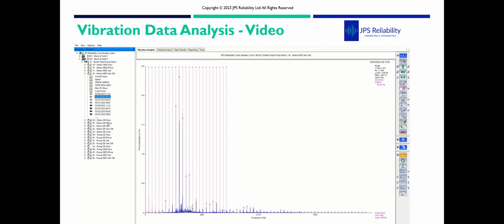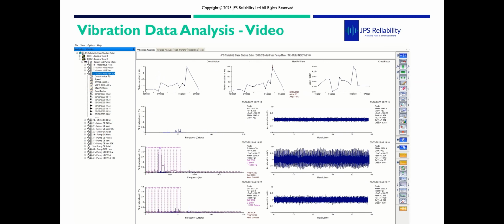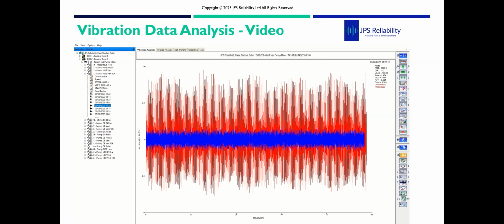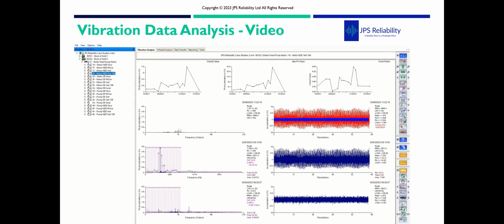We can jump into the peak view data, and you can see here the change straight from when the bearing was with defect and no defect. But the big giveaway, as I say with these bearings, is your high frequency. You can see it there. And what's pretty cool, again, another function of the software, is we can actually overlay before and after. So when you want to show someone, look, this is the bearing screaming, you know, 20, 30, 40 Gs, and this is the bearing after. Okay, so that's a quick little squiz at the data, how we analyzed it, how we came up with that. It was actually EDM to the outer race.